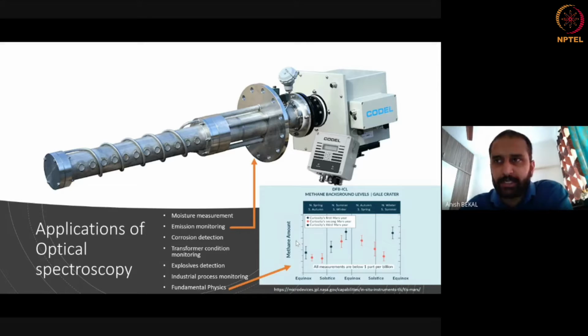Also you have corrosion detection. Hydrogen sulfide, which exists in small parts in natural gas, can corrode the metal of the pipe and lead to explosions. Several explosions have occurred because of corrosion, and even concentrations as low as 4 parts per billion are sufficient to cause corrosion and explosion of the pipeline over the long term.